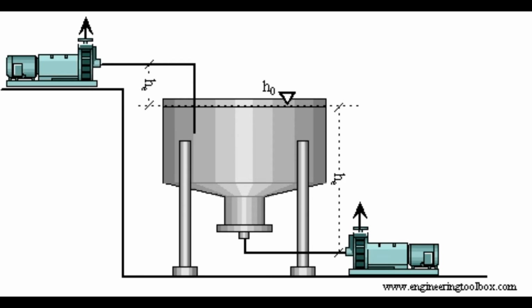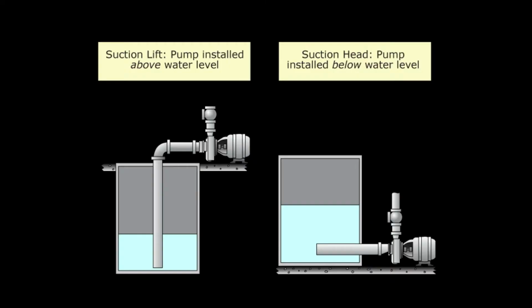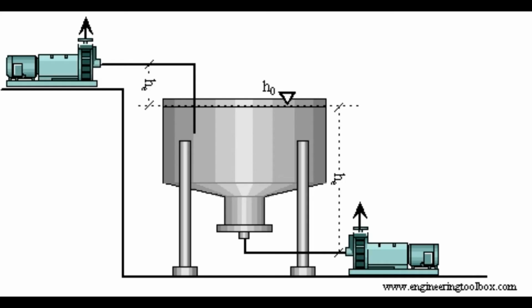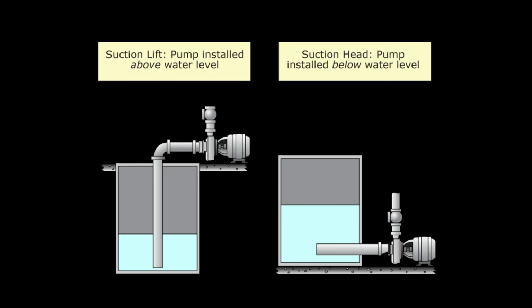4. Pump inlet conditions. You don't want to starve a pump. System net positive suction head, NPSH, available is calculated by knowing pump inlet pressure and liquid vapor pressure. Always make sure NPSH available exceeds pump net positive suction head, NPSH, required.